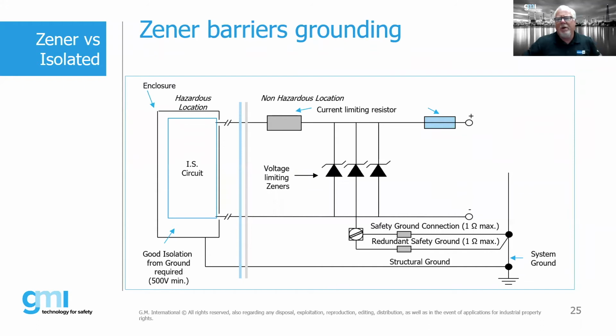Now, Zener barriers from a grounding standpoint. Sometimes people will ask the question, and I don't know if this was asked, I think we had this in the last seminar, but a lot of times people will utilize two conductors for your safety ground, for your IS earth. So you can see there's a safety ground connection here and a redundant safety ground, right? That is tied into, again, the safety system earthing ground, if you will.